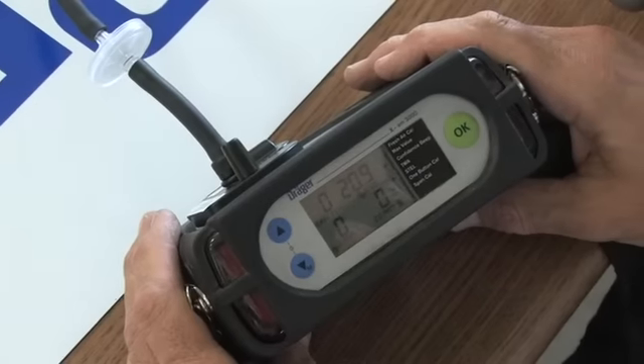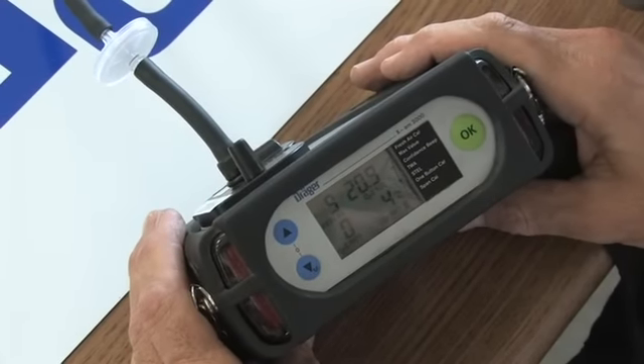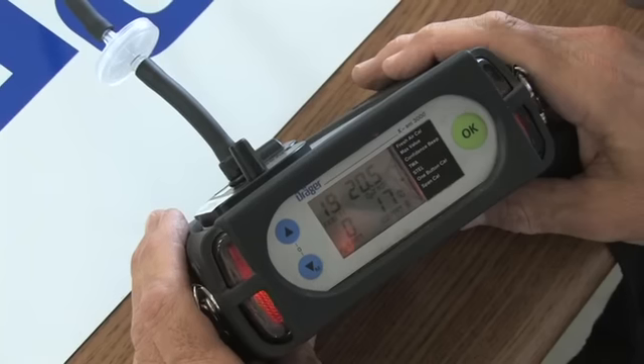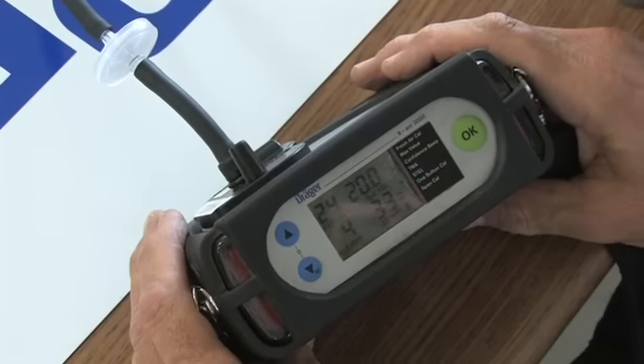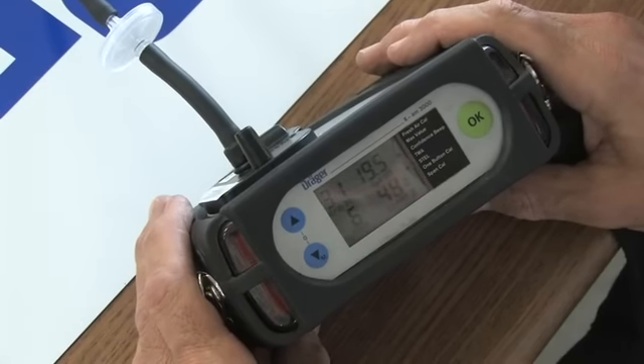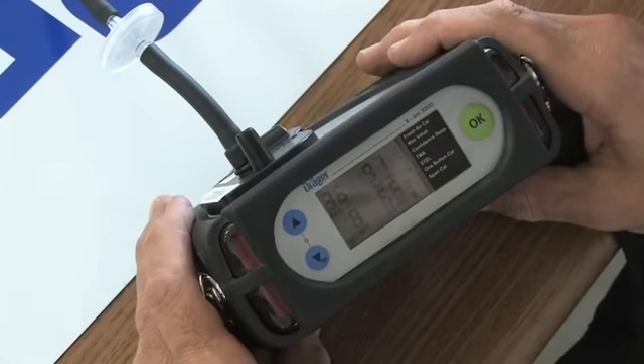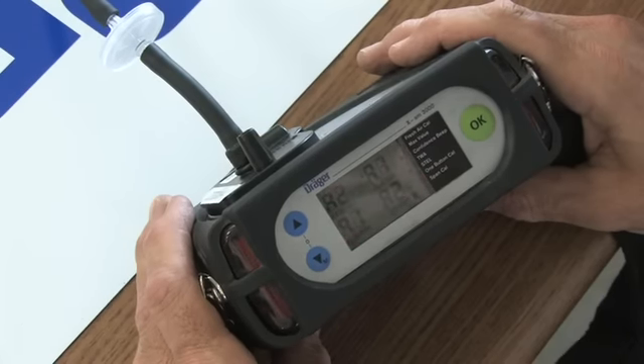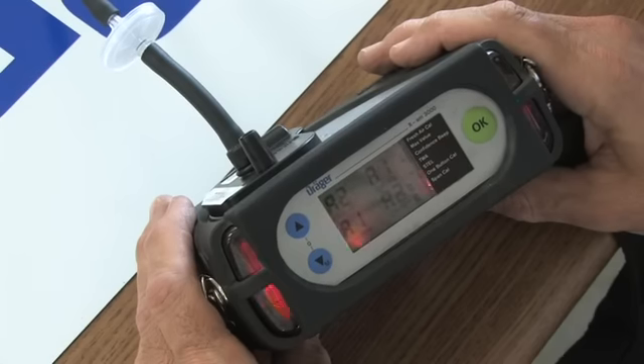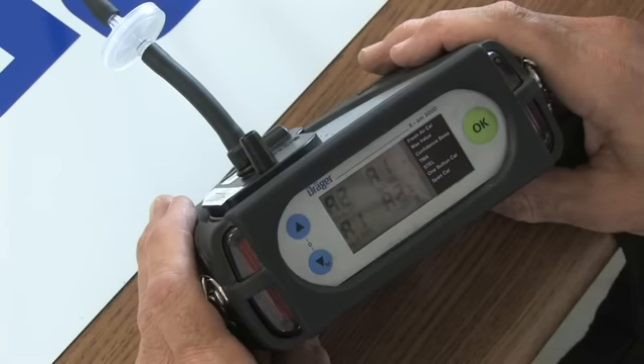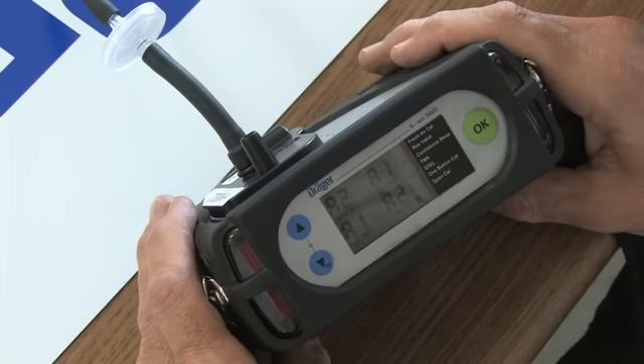LEL, movement, CO movement, oxygen's dropping. There's our A2 alarm, which is our double pulse alarm. So far, the combustible detector is winning the race by just 1 percentage point. It's already hit the 46 mark, so it has passed. H2S is gaining ground at 20. CO is also gaining ground.